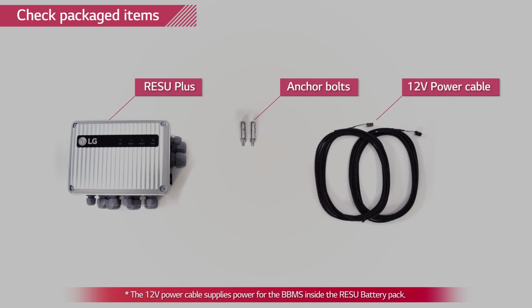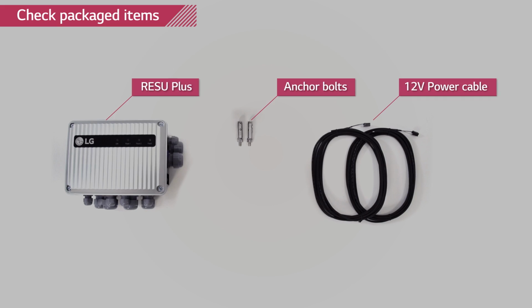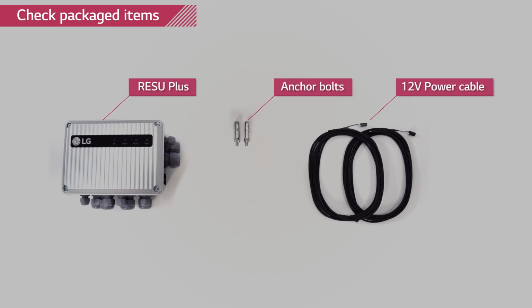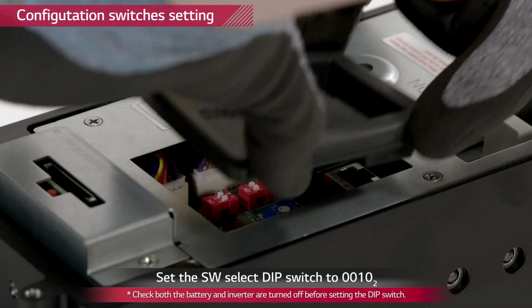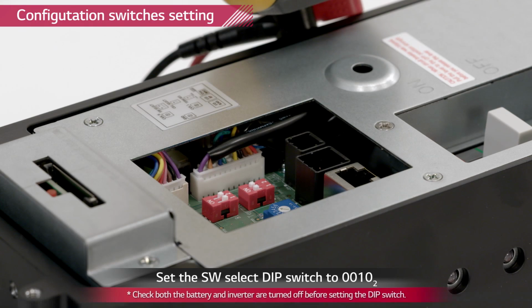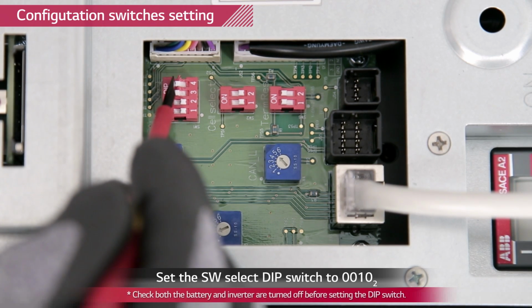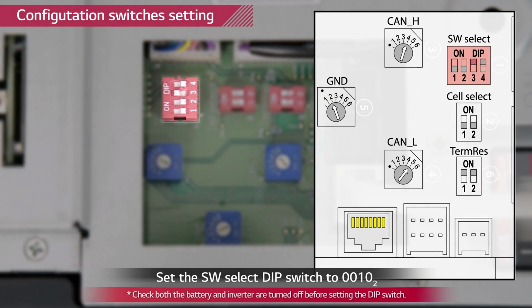Make sure you turn off the battery and its inverter before you install the RESU Plus. The dip switch setting of the battery pack has to be changed to LGC multi-mode. Remove the rubber switch cover and change the dip switch setting to LGC multi-mode.